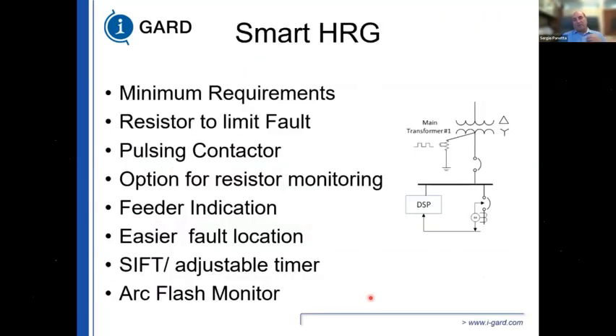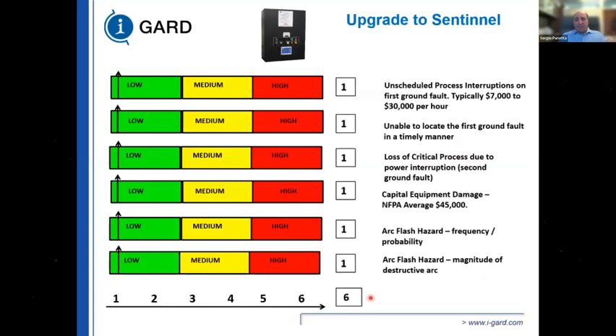One thing we've done is we've listened to our audience and said, it's great that I have a high resistance grounded system and I decrease the probability of having an arc flash event, but I want to reduce the severity of having an arc flash as well. Why am I spending the money on a resistance grounded system if I don't get both benefits out of it? So we've created an arc flash monitor to clear the fault in a timely manner and have the benefits of decreasing the probability of having a fault as well as the severity of having a fault. When you do that, everything goes to 1 and your risk assessment meter is at 6.